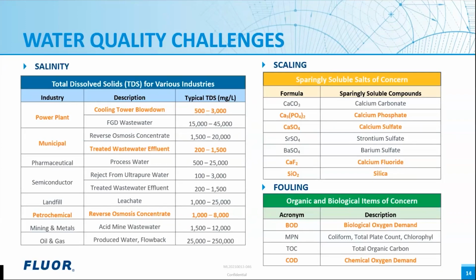As the recovery of the plant is increased, so is the risk of scaling and fouling. Some of the more potent scaling compounds are from calcium and silica, as highlighted in orange in the table on the top right. To minimize precipitation and scaling, it is important to establish a well-designed scale control measure, such as anti-scalant dosing or selective ion separation technologies, such as softening, ion exchange, and nanofiltration, to limit exceeding the solubility limits.